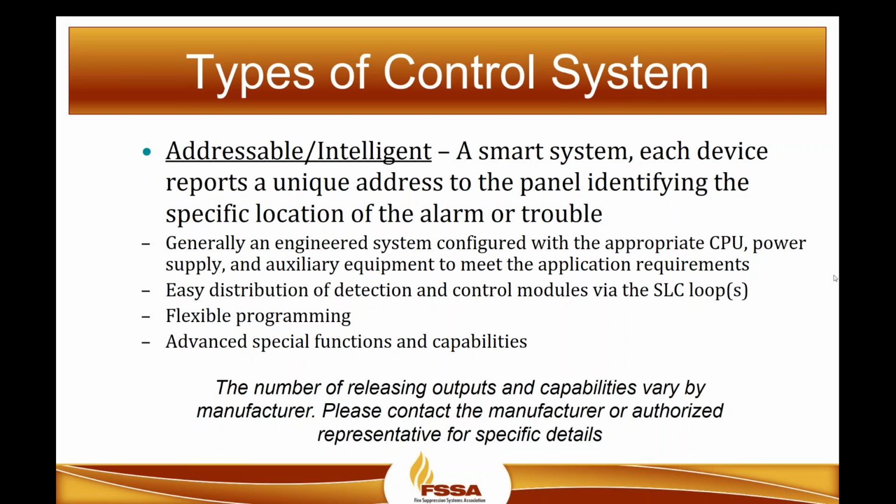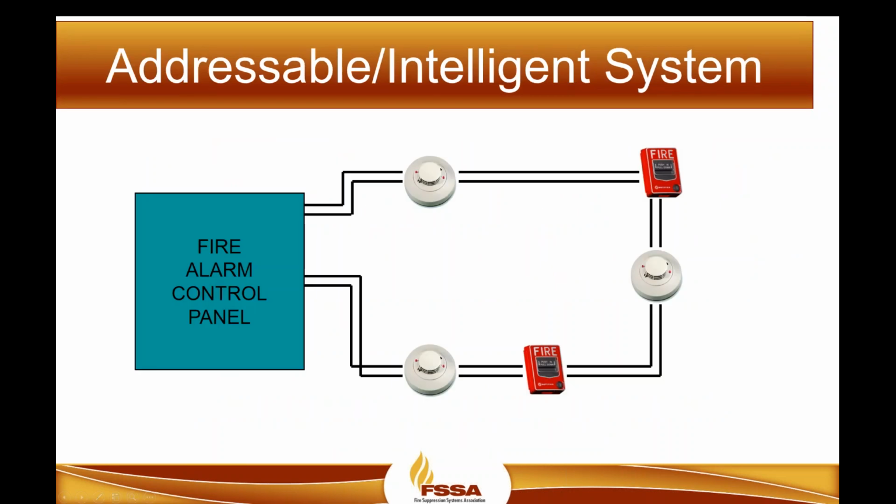And it comes up: where is our price point? Where's our break point? When do we go with individual conventional detection and control panels versus one large addressable? How many zones? How many releasing zones? Cost-wise, we start thinking about it around three hazards, and you're really going to start to be more cost-effective with an intelligent addressable system, offering a lot more information locally at the front of the panel and being able to annunciate that remotely is really an advantage.